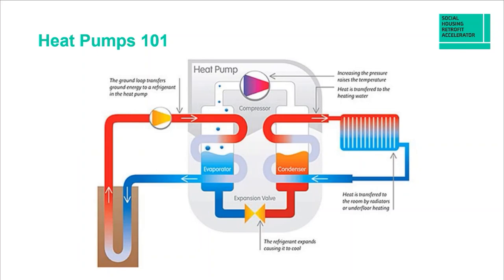This is where the science takes place. From school physics: you can't compress a solid or a liquid, but you can compress a gas — and when you compress a gas, it gets hot, just like pumping a bicycle pump with your finger over the end. We can control the output temperature, which is how we keep efficiency as high as possible — we only ever create a temperature commensurate with what's happening outside. This is the key to weather-compensated control: when it's very cold outside we generate higher temperature into the radiators, and as the air temperature improves we allow that temperature to reduce, always keeping compressor work to the minimum required.